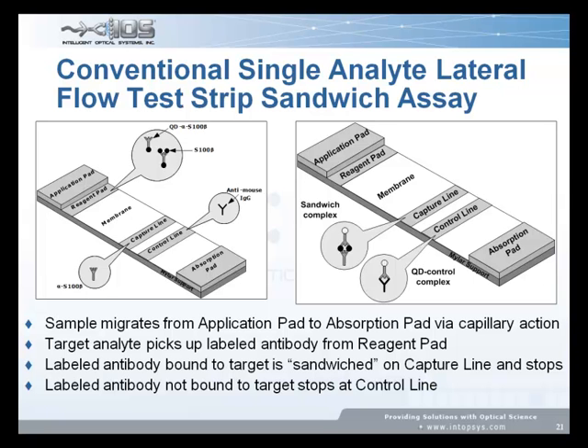What we've been able to bring to this is the ability to quite easily measure multiple analytes on a single test strip. So for those of you not familiar with it, the way it works is you put a sample down on one end, and I guess you could call this picofluidics. It's actually just capillary action that moves the sample along this strip. And as the sample moves, it picks up various reagents and encounters various other substances. I'm going to keep this at a relatively simple level. So you can label your targets with antibodies and fluorophores. You can do essentially a sandwich immunoassay, all without any moving parts, all just on this miraculous piece of, well, it's not paper anymore, but it's essentially like really fancy filter paper.